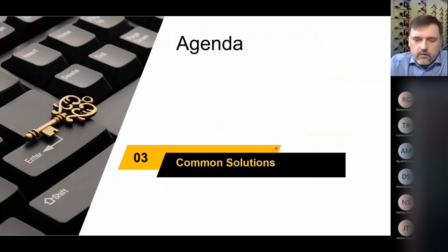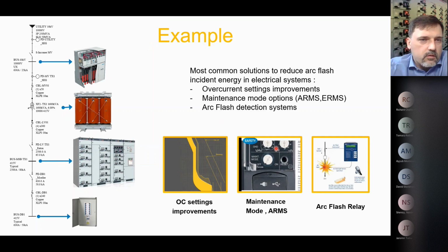So, common solutions. I show you a general overview, but I will go step by step to explain what we can do and how I did it in the project. This is from a real project I did. I just changed the names and took some part of it, where we have a medium voltage switchgear, a transformer, low voltage switchgear, and then the panel board downstream. And most of the time, I would say 90% of projects, will use overcurrent protection, maybe maintenance mode if that's applicable or not, because that depends on what kind of hardware we have, and arc flash detection systems, arc flash relays.